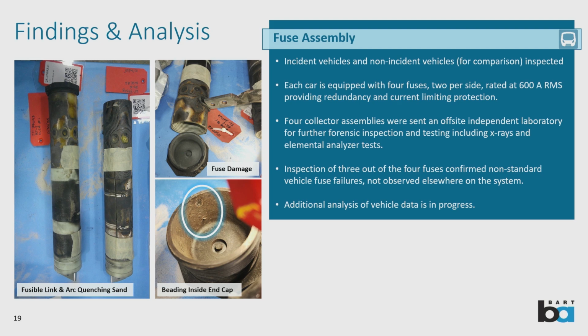More evidence came from looking closely at the inside of the end cap, where there is beading—tiny metal balls indicative of a possible high energy thermal event or arcing within the end cap, possibly originating from the lug itself. However, this is still under analysis.